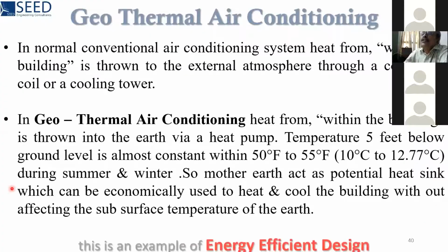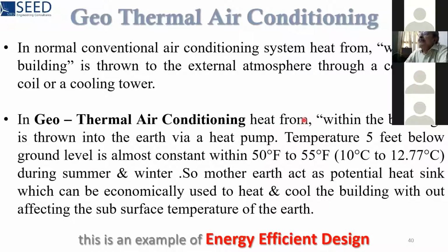So in a geothermal air conditioning system, heat from within the building is thrown to the earth via a heat pump. Temperature 5 feet below the ground level is almost constant between 50 degrees Fahrenheit and 55 degrees Fahrenheit during summer and winter. So Mother Earth acts as a potential heat sink, which can be economically used to heat and cool the building without affecting the subsurface temperature of the earth.